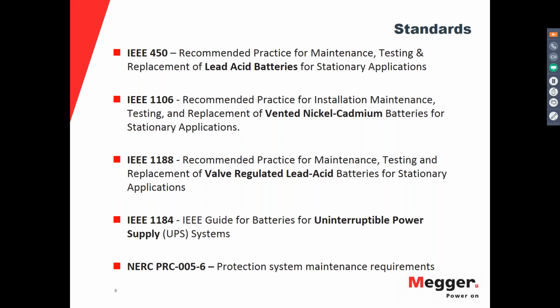We have the lead acid batteries, that is IEEE 450. Also, for the valve-regulated lead-acid batteries, we have 1188. And for vented nickel-cadmium batteries, we have 1106. Those are the three types of batteries that we're going to be referring to today. Everything I've prepared for this presentation is related to these types of batteries, without making direct reference to them. Everything in these slides relates to these batteries, and there are some notes there to distinguish between them.